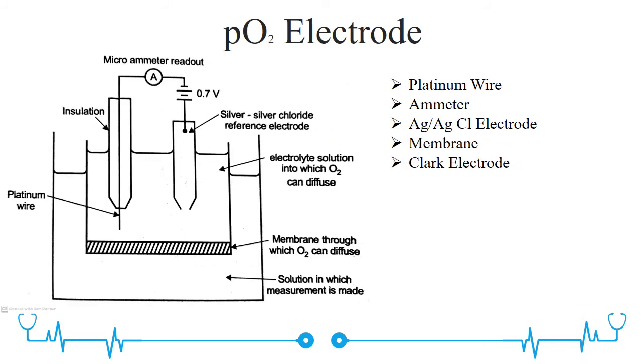Next comes the PO2 electrode. The oxygen electrode is a piece of platinum wire embedded in an insulating glass holder with the end exposed to the electrolyte. Oxygen from the solution under measurement diffuses through the membrane. The bottom of the vessel contains the electrolyte with a membrane permeable to oxygen, and the top is sealed with a silver-silver chloride electrode.